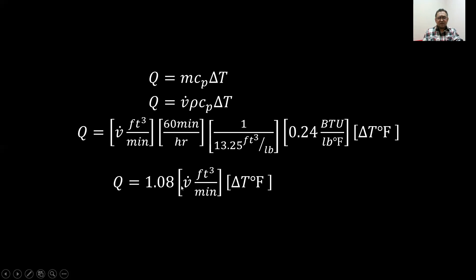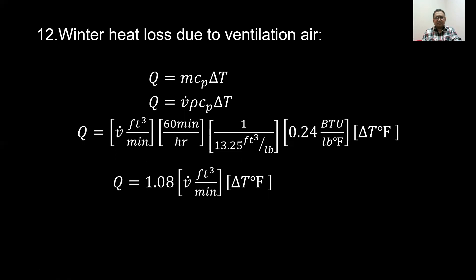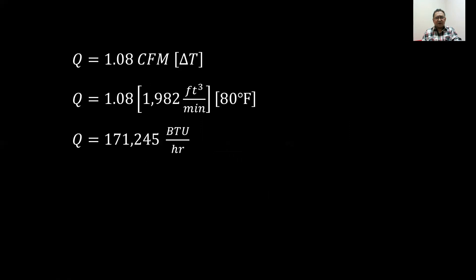We will compute the heat loss from ventilation air using Q equals m times C sub P times delta T, which simplifies to 1.08 times the volume flow rate in CFM times the temperature difference. For winter heat loss due to ventilation air: 1.08 times 1,982 CFM times 80°F equals 171,245 BTU per hour.